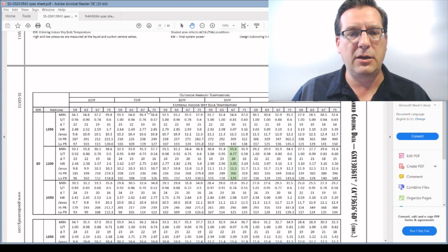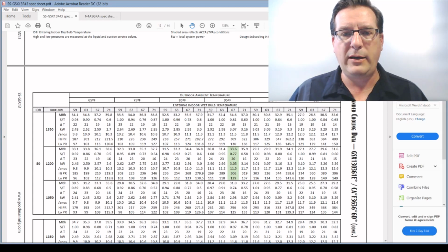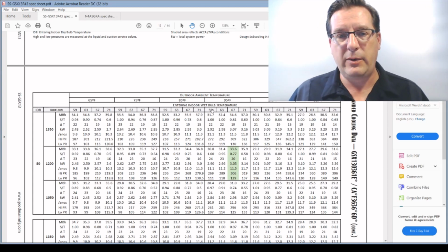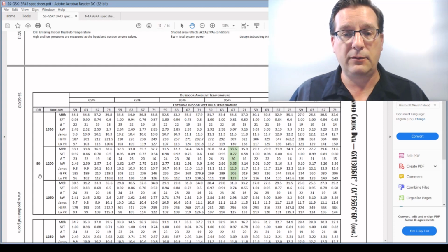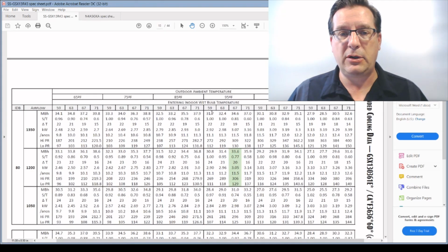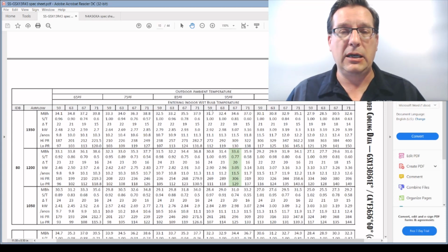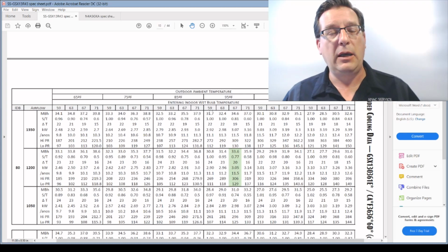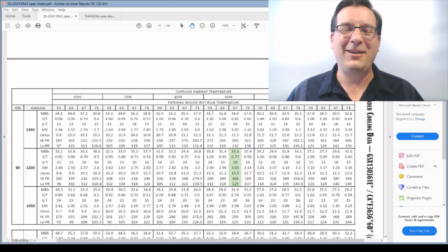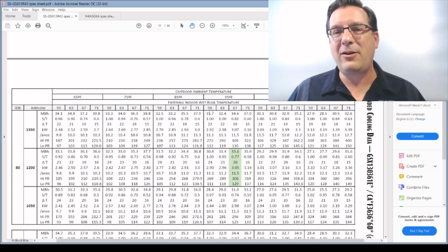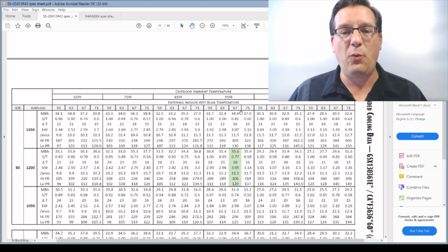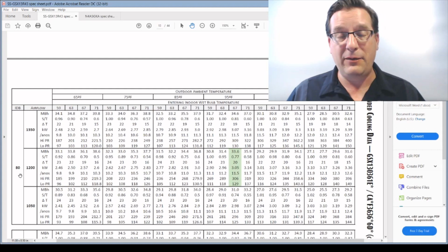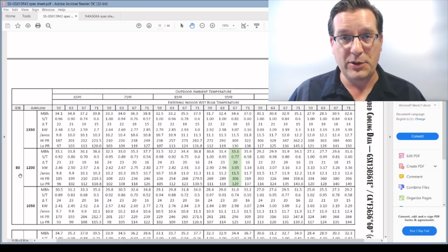Along this top here, ours is known as indoor entering wet bulb temperature. And you notice that we have 4 different selections for each outdoor temperature and indoor temperature combination. Essentially, wet bulb temperature is a representation of the heat energy contained in water vapor. And there's a real easy way to boil this down, pun intended. The higher the relative humidity, the higher the wet bulb will be for any given dry bulb temperature. If the dry bulb temperature was 80 degrees and the wet bulb temperature was 80 degrees, that would correspond to a relative humidity of 100%.